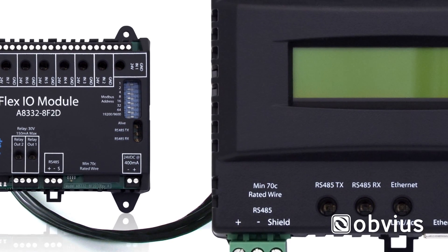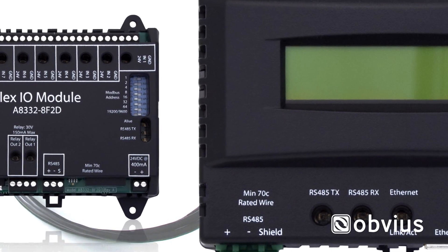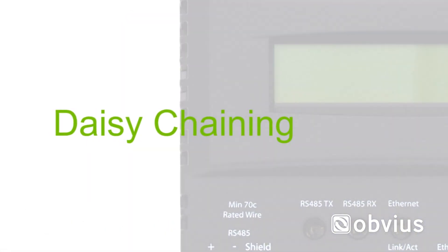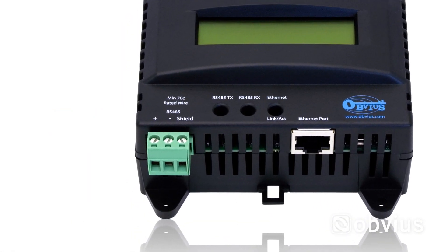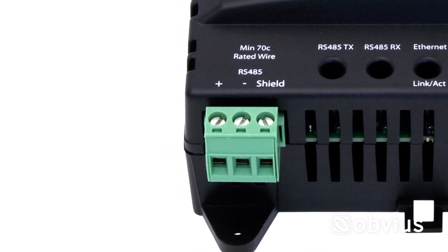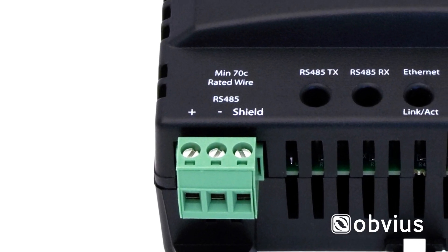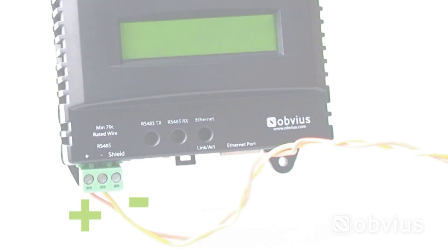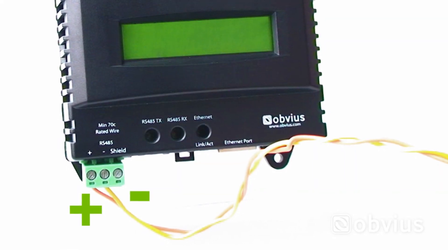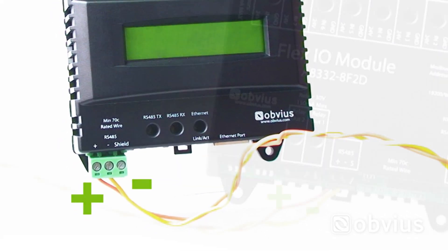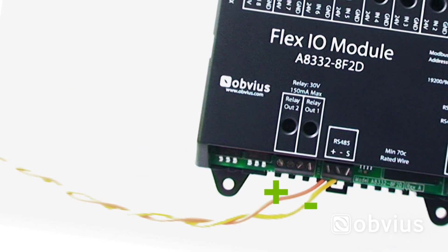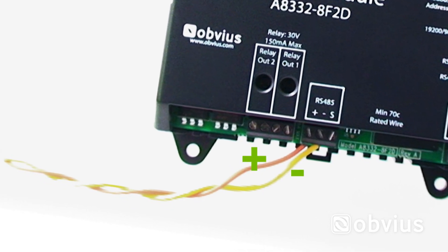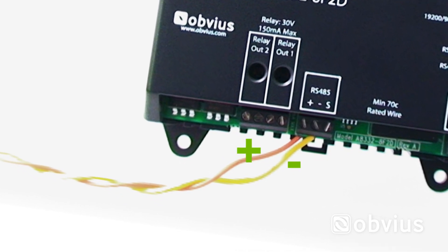Once each device has been provided a unique Modbus Address, users can begin connecting them to the AcquiSuite using a technique known as Daisy Chaining. Begin by identifying the Modbus RS-485 terminal on the data acquisition server, consisting of positive, negative, and shield terminals. The most important factor when Daisy Chaining is to maintain polarity, meaning that the positive line is only connected to other positive terminals of the devices until connected to the DAS. Repeat this technique for both negative and shield terminals.